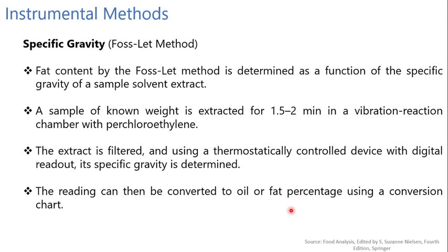extract. A sample of known weight is extracted for 1.5 to 2 minutes in the vibration reaction chamber with perchloroethylene. Then the extract is filtered, and using the thermostatically controlled device with digital readout, its specific gravity is determined. The reading can be converted to oil or fat percentage using a conversion chart.